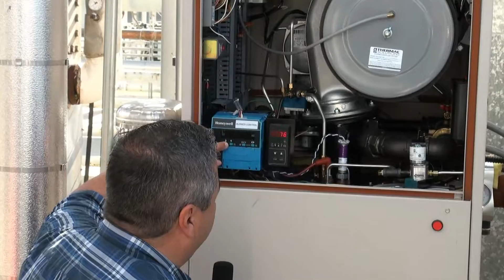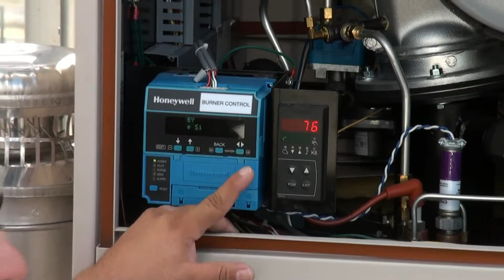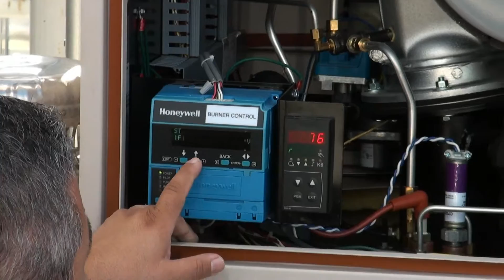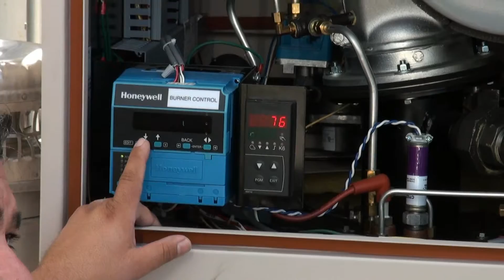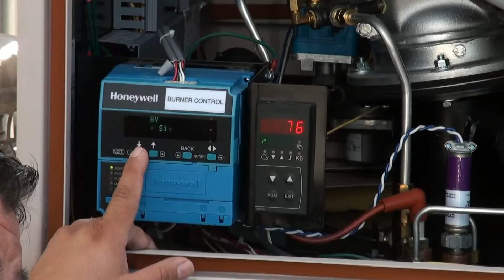Usually for normal operation, the thing is sitting on standby or run, and the next line item is flame signal. When the boiler's running, that flame signal says 5. Right now it's at 0, obviously because the boiler's off. But you can scroll through. So the 5 is maximum? 5 volts is the maximum. When it's off, it's 0. But when it's modulating? It's still 5 volts, because that's just the pilot voltage going to the pilot light.